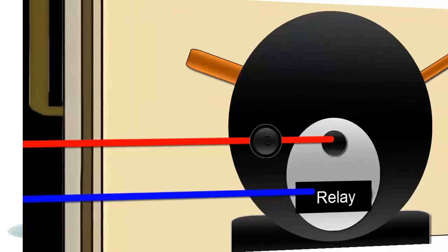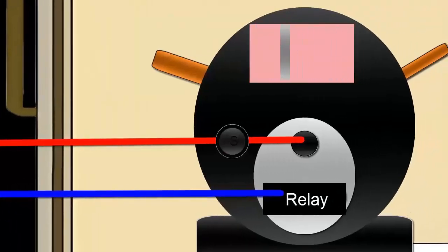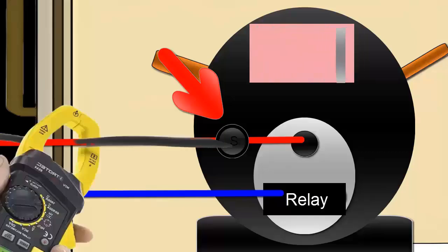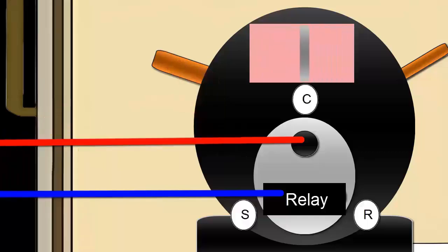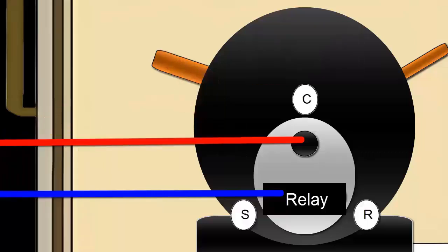4. Faulty thermal protector. A defective thermal switch may accidentally disconnect the compressor. To check, remove the thermal protector connected to the common pin of conventional compressors. Connect the power wire directly to the common pin temporarily and see if the issue resolves.